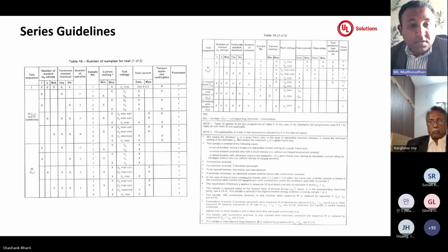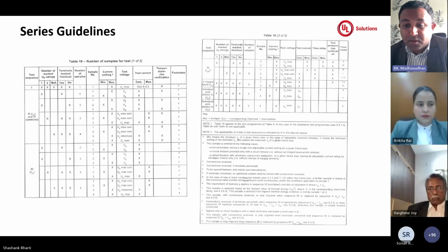For example, in sequence 1, if the product has multiple voltages and also multiple currents, it gives a reference for what selection of voltage to be taken and what selection of current to be taken to perform this sequence 1. So in this case, for any number of declarations you make, we need to pick one sample from the standard, and the test to be carried out will be covering the complete range.